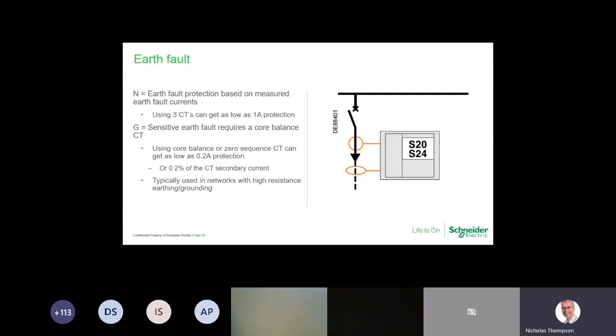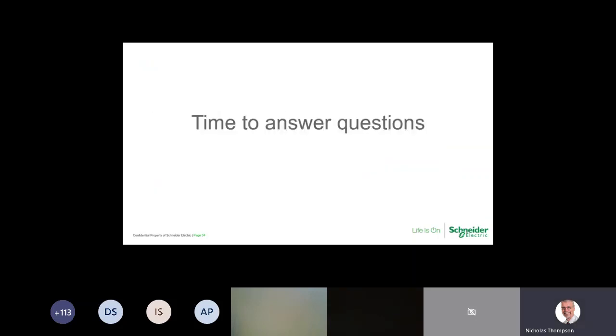So for sensitive earth fault, we need the 4th CT, and that's the CT which will go around all 3 cores, and you can then get it down to 0.2% of the secondary CT. So you can get down to really low earth fault current protection. And as it says there, high resistance earth grounding networks.